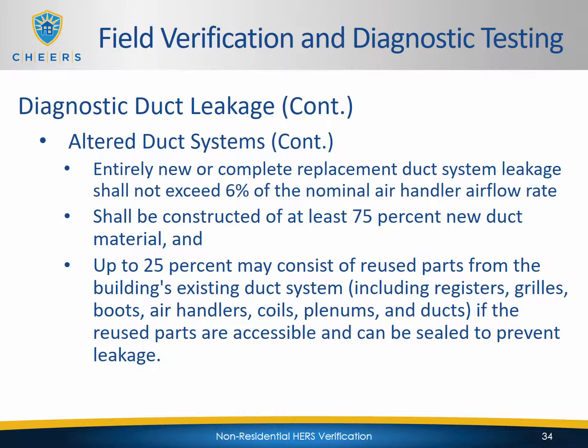For new duct systems in new construction, the leakage rate must not exceed 6% of the nominal air handler airflow rate. For the 2016 standards, residential dropped from 6% to 5%, whereas non-res has stayed at 6%. An entirely new or complete replacement duct system consists of at least 75% new duct material — including ductwork, wyes, register boots, and other components. The remaining 25% may consist of reused parts from the existing system if those parts are accessible and can be sealed to prevent leakage.